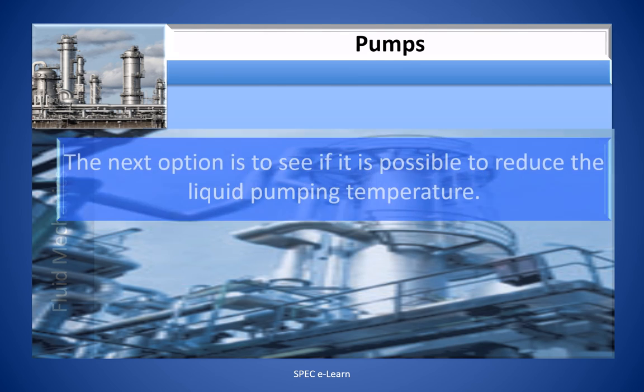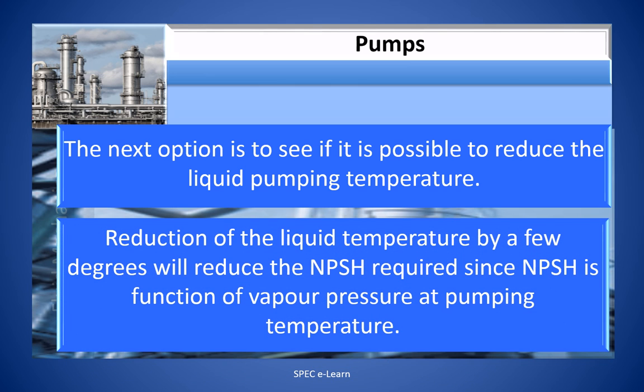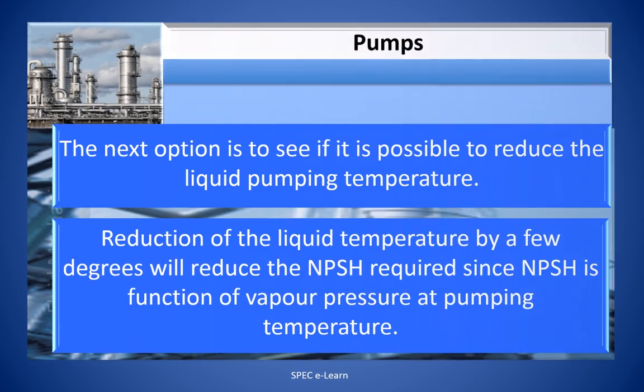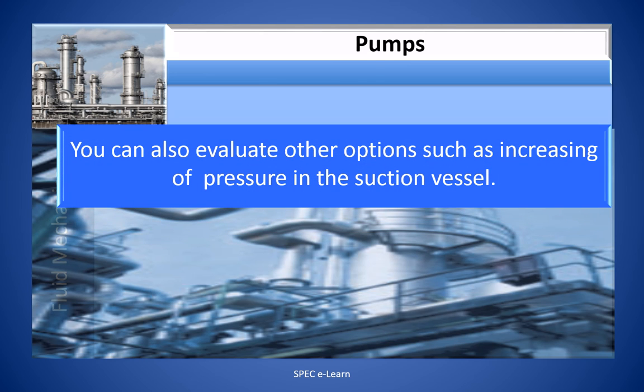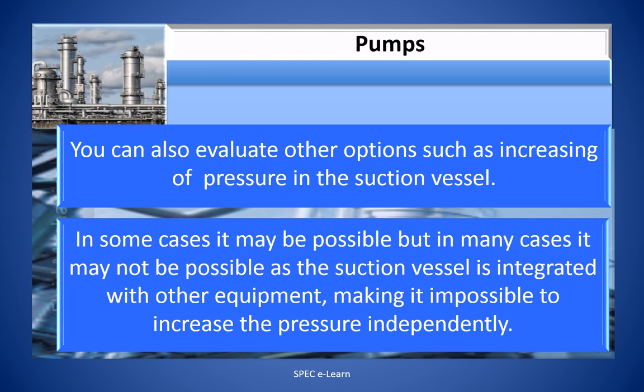The next option is to see if it is possible to reduce the liquid pumping temperature. Reduction of the liquid temperature by a few degrees will reduce the NPSH required, since NPSH is a function of vapor pressure at pumping temperature. You can also evaluate other options such as increasing pressure in the suction vessel. In some cases it may be possible, but in many cases it may not be possible, as the suction vessel is integrated with other equipment making it impossible to increase the pressure independently.